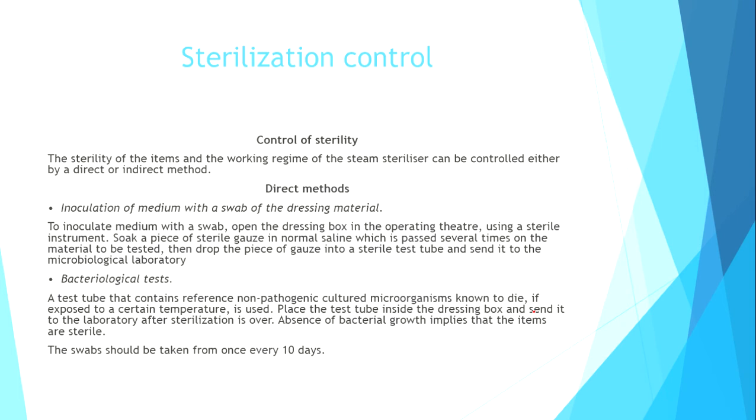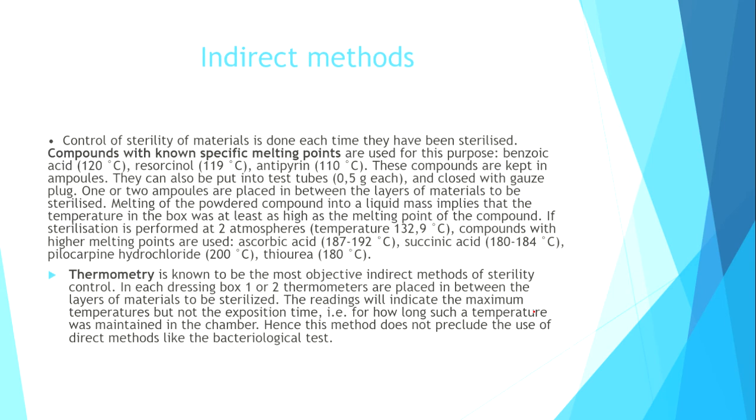Bacteriological tests. A test tube that contains a reference non-pathogenic cultured microorganism known to die if exposed to a certain temperature is used. Place the test tube inside the dressing box and send it to the laboratory after sterilization is over. Absence of bacterial growth implies that the items are sterile. The swabs should be taken once every 10 days.